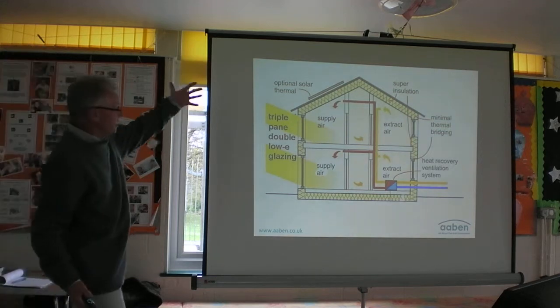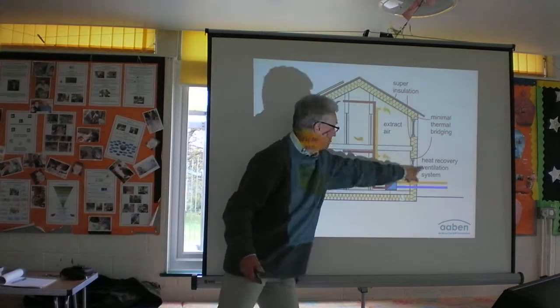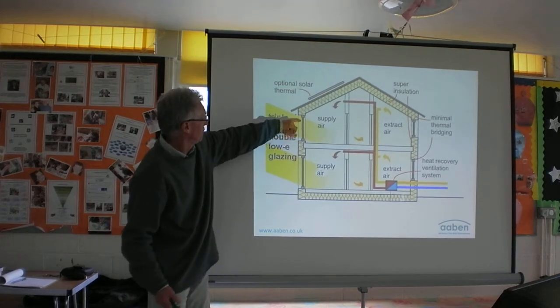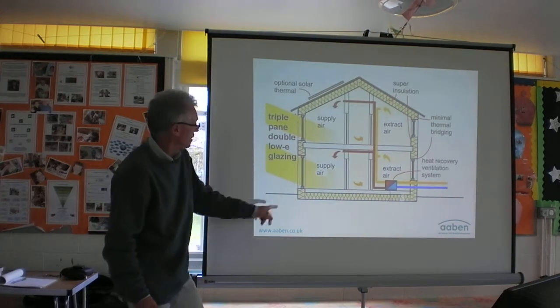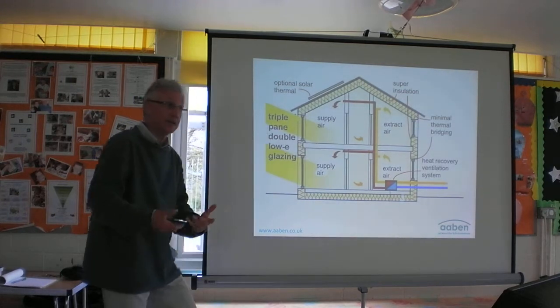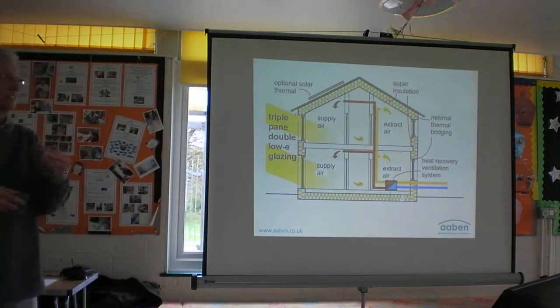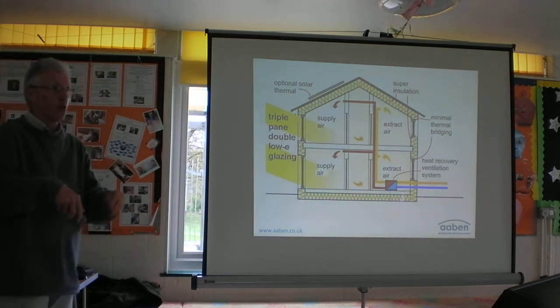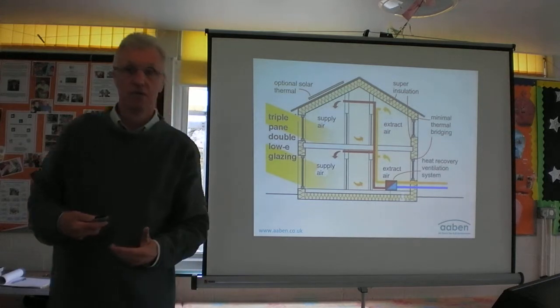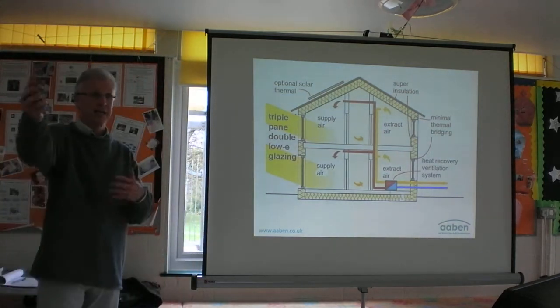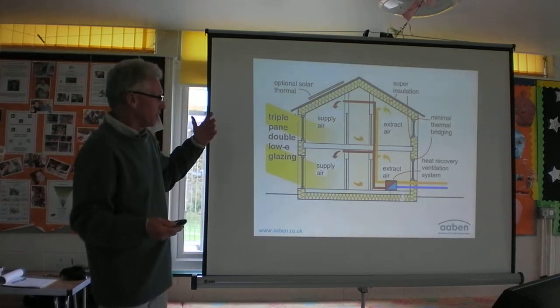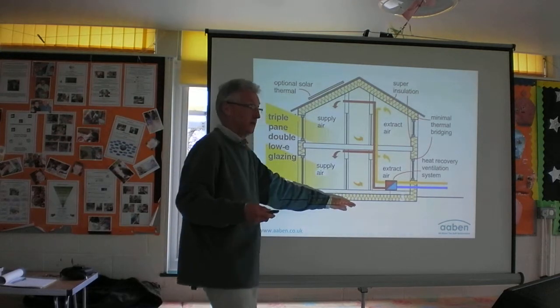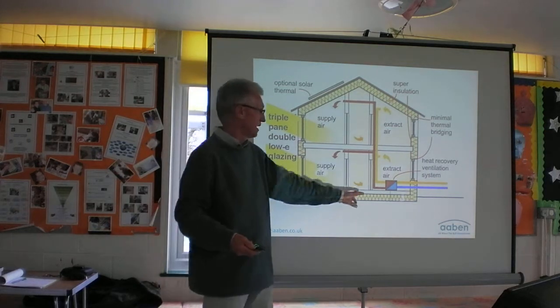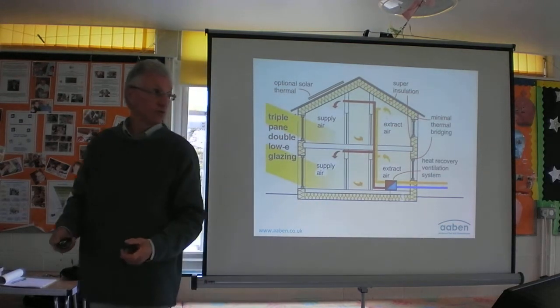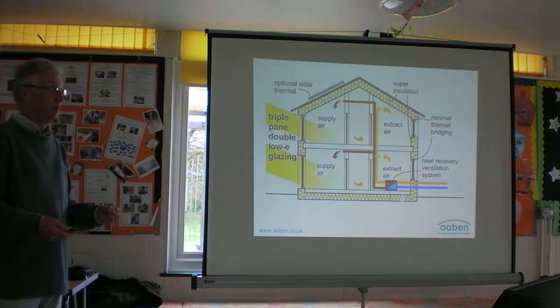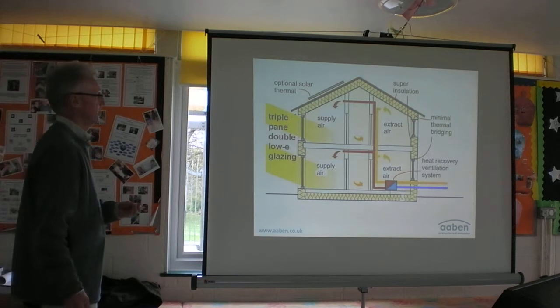So there's a sort of diagrammatic passive house. It's insulated all the way around. There's no breaks in the insulation except where there have to be for things like windows. It's got an airtightness layer to limit the air losses. Now what we're doing here is we're not sealing you in a plastic bag, we're controlling the ventilation instead of leaving it uncontrolled. Most houses are ventilated by default, gaps. Okay? Because we're controlling it, we are actually making it very airtight. The air's not flowing in from the outside naturally. We've got to manage that, and manage it with a heat recovery ventilation system, which recovers most of the heat from the warm, stale air before it chucks it out and puts it back into the incoming air.